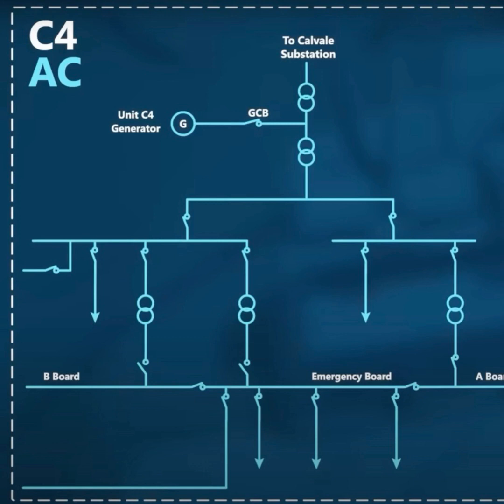Tracing a single line on the wall whilst chaos is going on around you, finding the right breakers and determining what's on and what isn't on when you're under immense pressure is much, much harder than you think. This is why it's key to have good local state indication as well as manual override controls. They had the manual controls, but it's unclear if they had good local indication as well and may have hesitated.